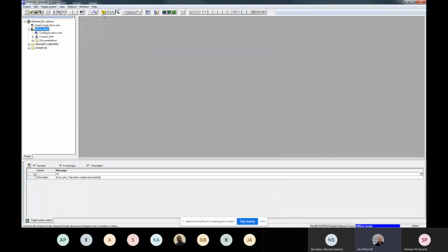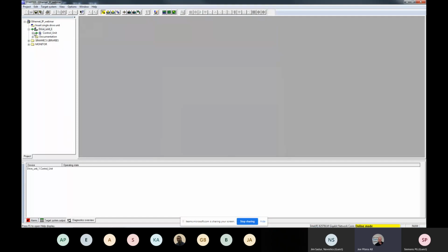At this point, we can go online with that drive unit, and we will see that the offline has not been configured, but the online knows there's a PM240-2 attached to this. We are going to load the hardware configuration to my PG at this point. Now it knows it has a full drive system here.